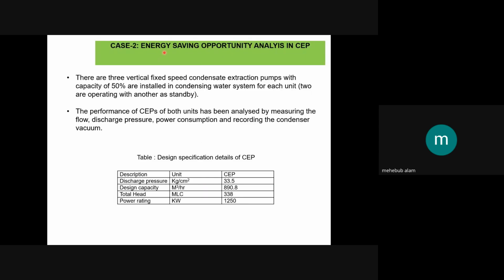Now the second case study is the condensate extraction pump. We have 3 condensate extraction pumps. 2 pumps are operating at a time, and the third pump is kept on standby. This is the design specification of the condensate extraction pump. The power rating is 1250 kilowatt, which means 1.25 megawatt. So this is a very huge rating, and if we can save 2 to 3% of this 1.25 megawatt, that is also a huge saving.